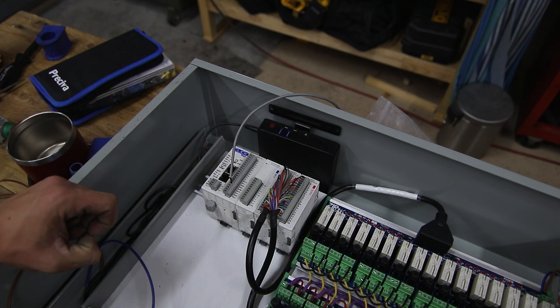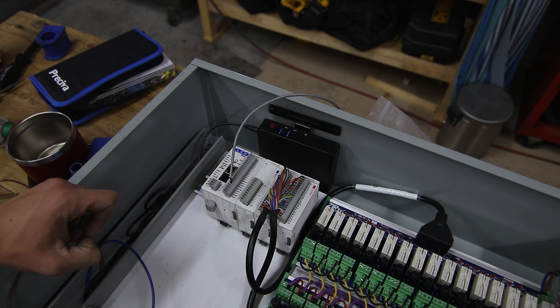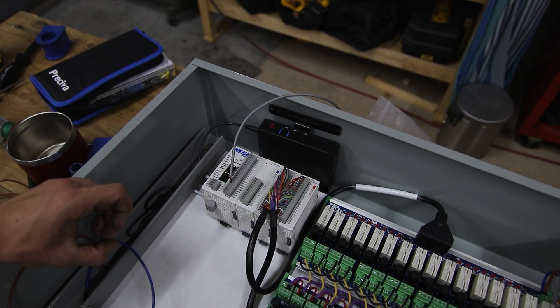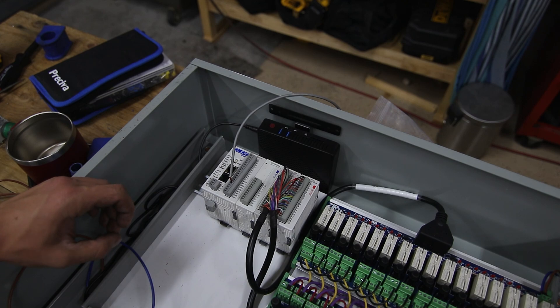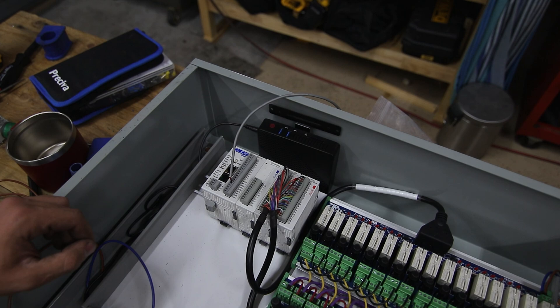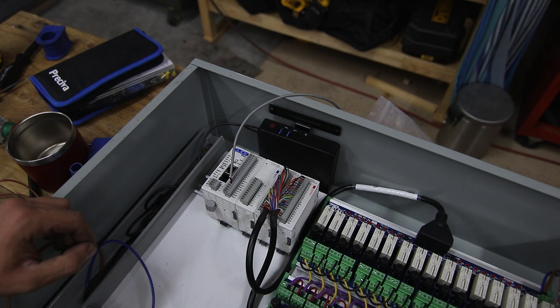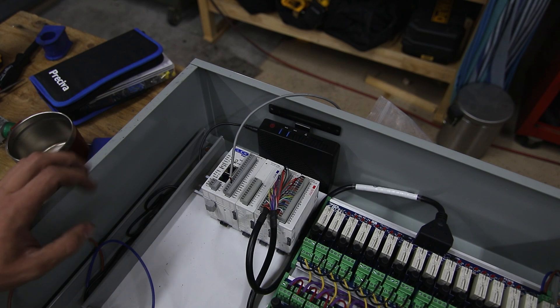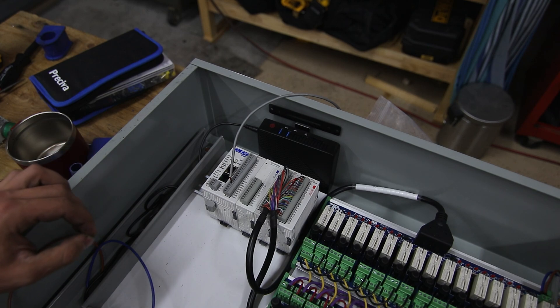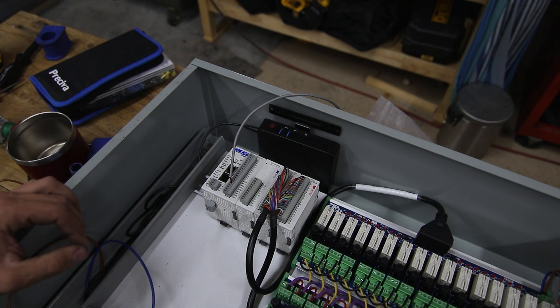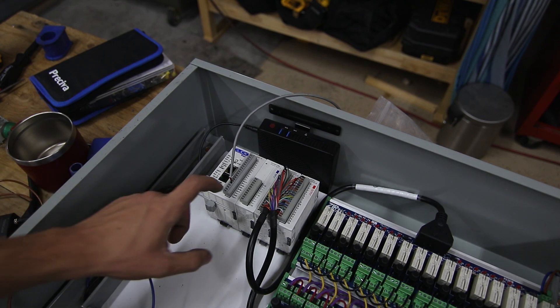Now I said a minute ago these are isolated from each other. But one thing that I found interesting in my other system is if there's a voltage difference between the two, like if they're not common to each other at reference to the same voltage, you actually get some really interesting measurements in the PLC and it'll seem like it's wandering and that's not very good if you're building a very robust system. So that's why all the shunts are bolted onto the same bus bar so in theory they're all at the same potential. They only have a minor deviation based on the amount of current running through the shunts.